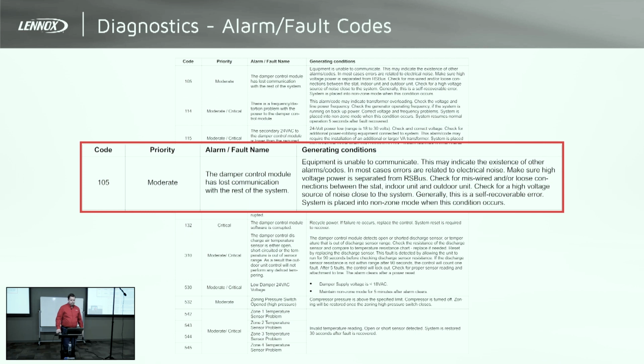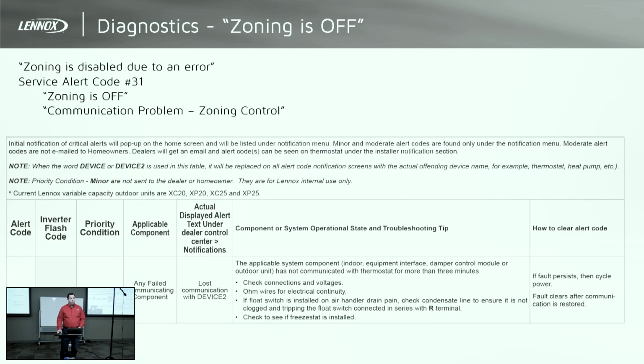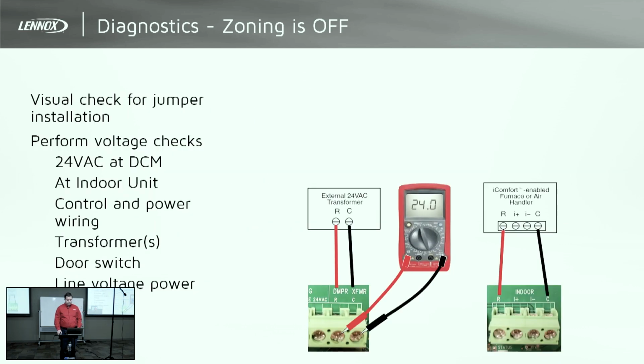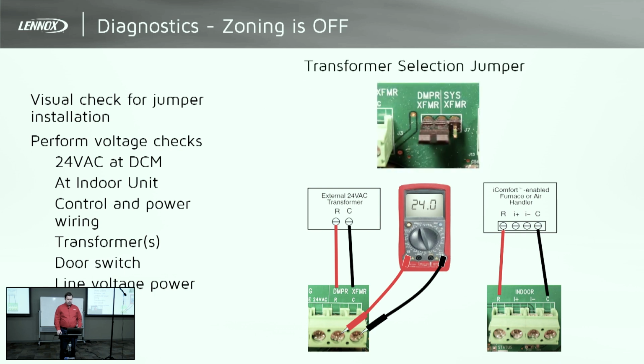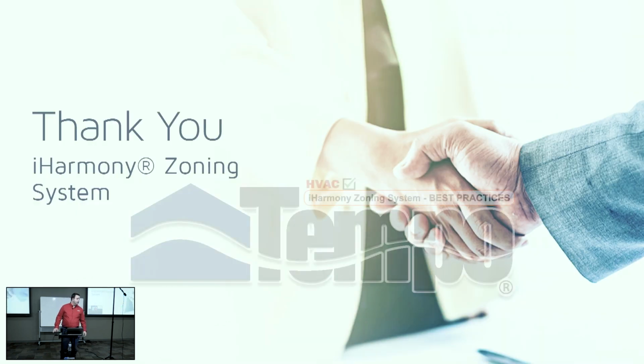And then you'll have your alarm codes. 105. We talked a little about communication issues. That's a specific code for the damper control module. The 31 is going to be a comm issue with any component on the system. We also talked about checking your transformer phasing, making sure the transformer selection is proper, and again, that's something you probably won't have to adjust in most setups. I think that's about it. Anybody have any questions? Sorry to zoom to the end of it.